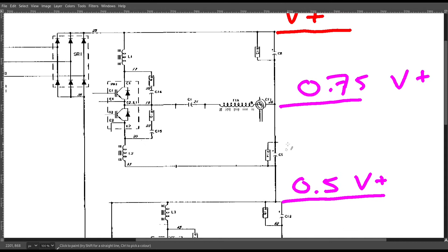Here's the input section on my machine, but the other ones are roughly similar. So what happens here is the front panel switch is S1, and when you turn it on, this is the main contactor, but it doesn't turn on immediately. The first thing that happens is L1 goes through this resistor and sort of bypasses the contactor, and then L2 does the same thing through this fuse and another resistor. And line 3 doesn't make it to the bridge rectifier yet, so you're only feeding one phase and via two resistors. And what this does is it allows the bulk capacitors to charge at a reasonable rate.